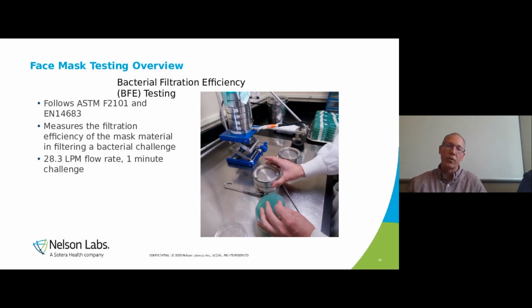With respirators, we test the whole device, but with face masks, we're testing just the material itself. So it's a smaller test area, and it is a lower flow rate. So this test is not as strict or not as stringent as the respirator test. We're only using a 28.3 liter per minute flow rate as opposed to an 85 liter per minute flow rate. And we challenge the material for 1 minute. We're aerosolizing a Staphylococcus aureus bacteria and then pulling a vacuum and measuring the concentration of the bacteria before it hits the sample, and then how much of that bacteria gets through the sample and impacts the agar plates.